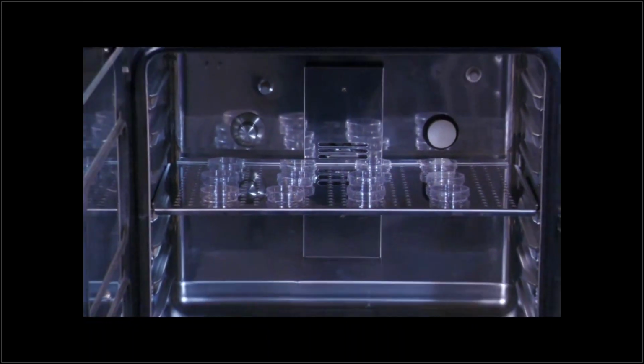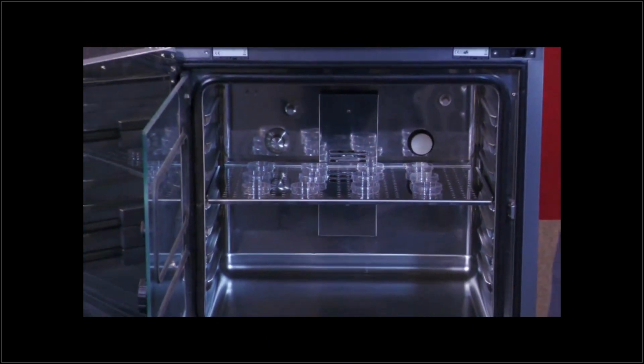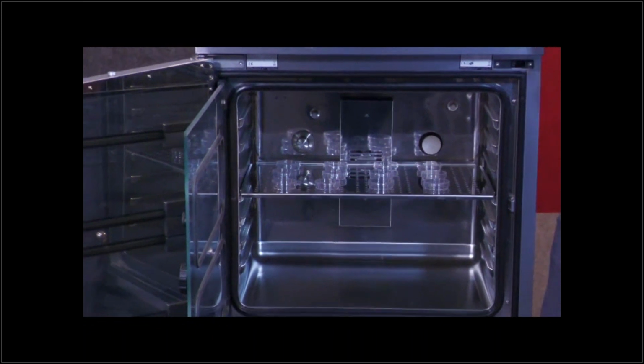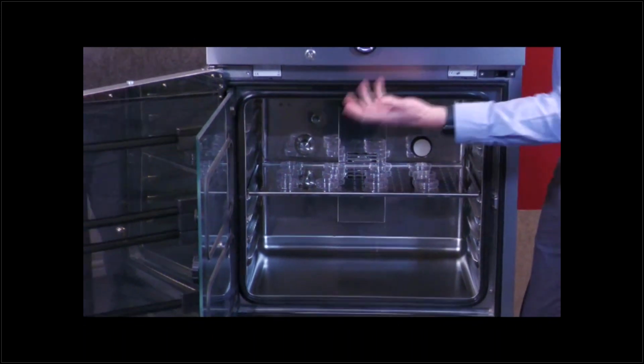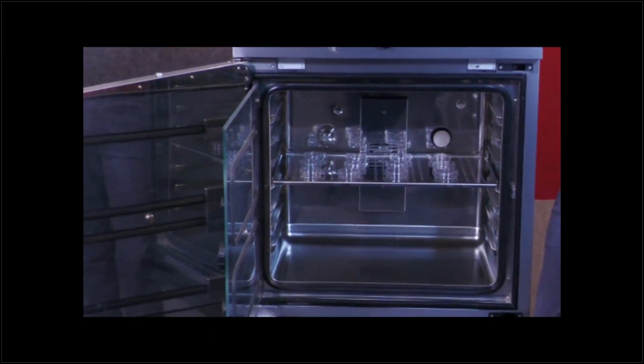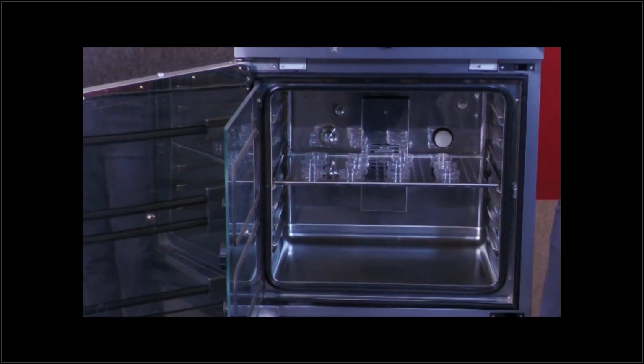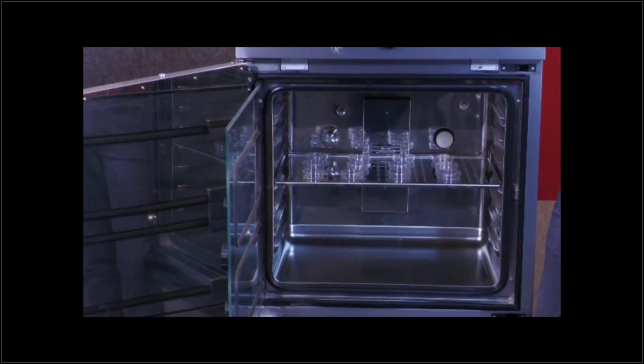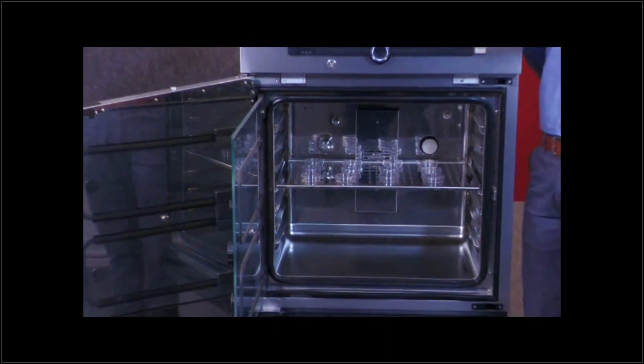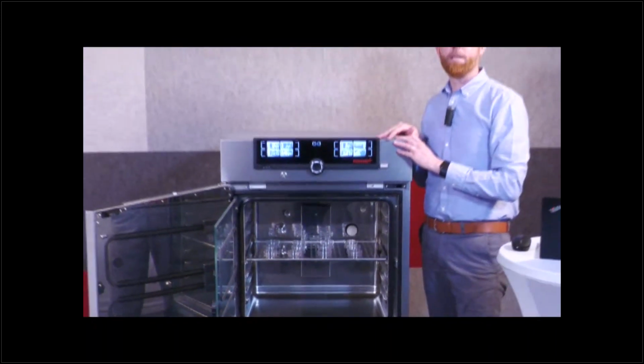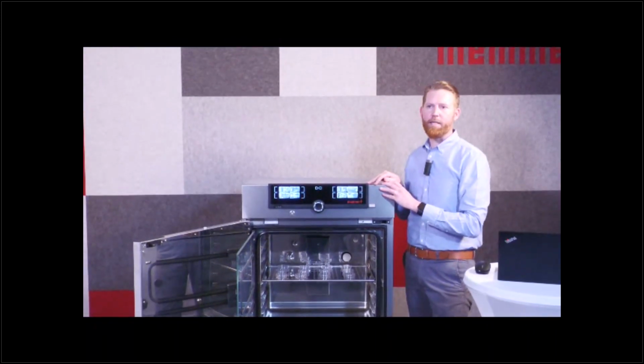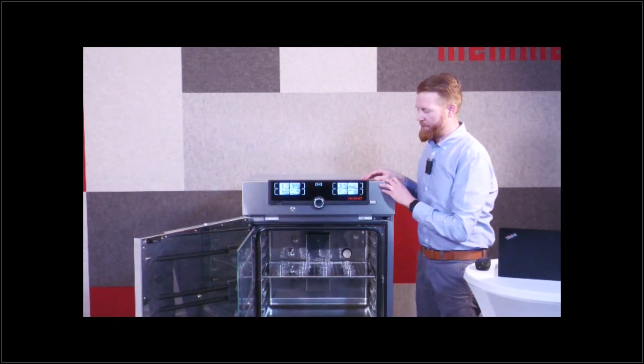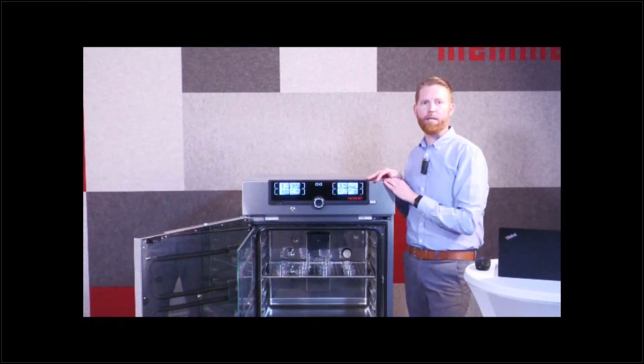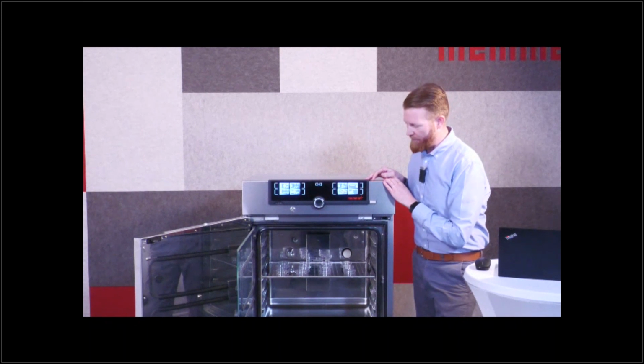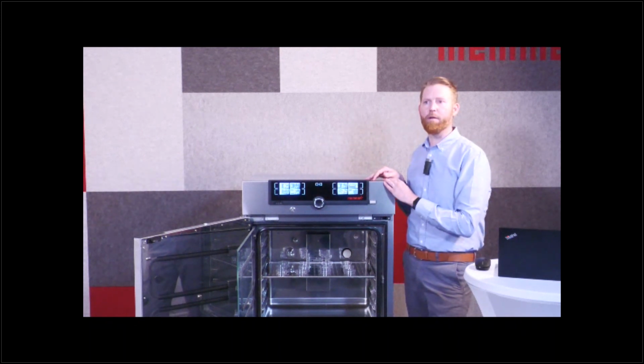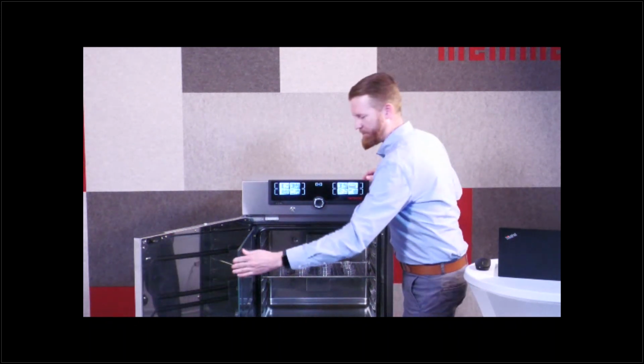A CO2 incubator from Memmert is equipped with a 6-sided heating, so all 4 sides, the rear wall, as well as the glass door, are heated. So we should make sure that we always keep the distance to the side walls. We're talking about a so-called 10% rule, which means that a distance of 10% of the complete volume should be kept from the side walls, from the rear wall, and from the door at the front.